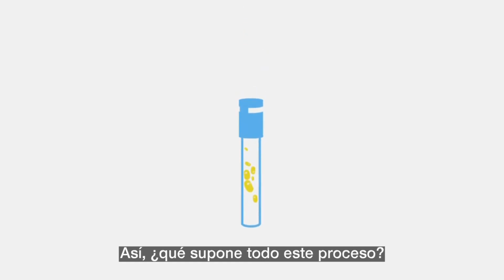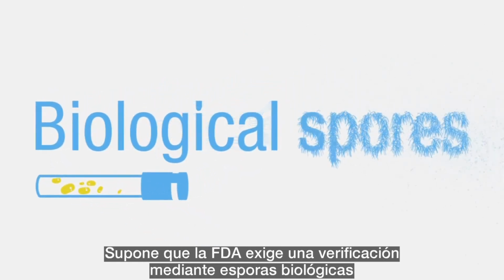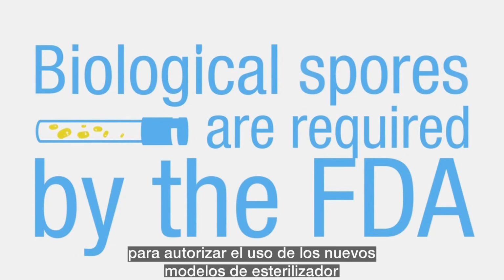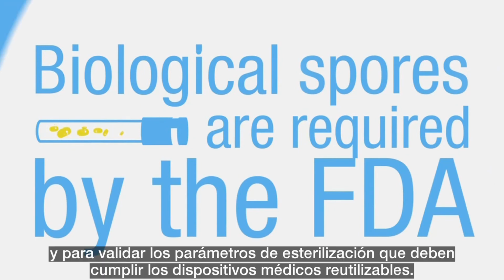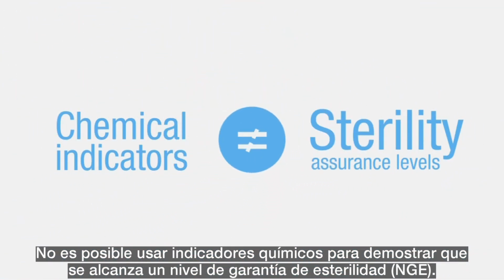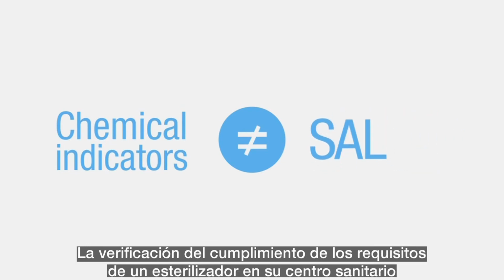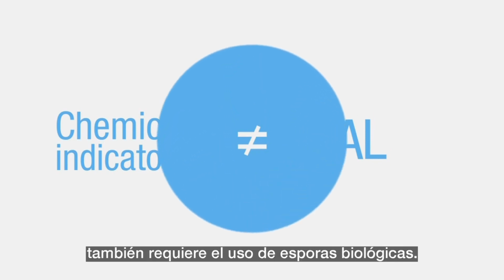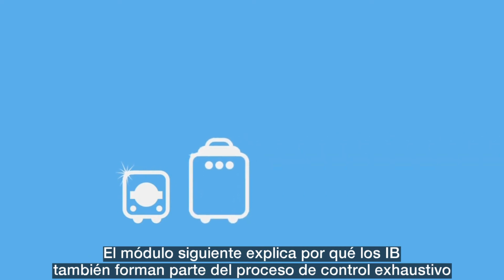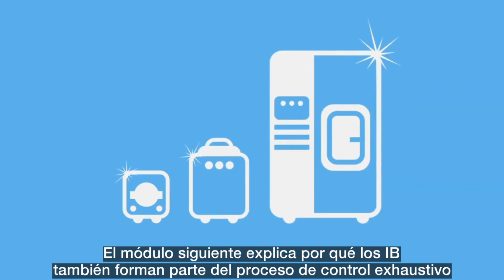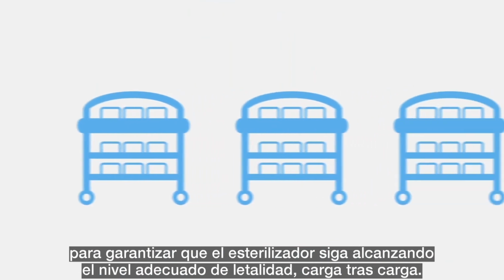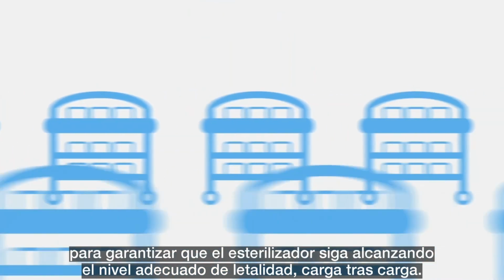So what does all this mean? It means that testing with biological spores is required by the FDA for clearing both a new sterilizer model and for validating the sterilization parameters required for reusable medical devices. Chemical indicators cannot be used to demonstrate achievement of a sterility assurance level, SAL. Sterilizer qualification testing at your facility also requires the use of biological spores. The next module will discuss why BIs are also a part of your comprehensive monitoring process to ensure your sterilizer continues to deliver lethality on a load-to-load basis.